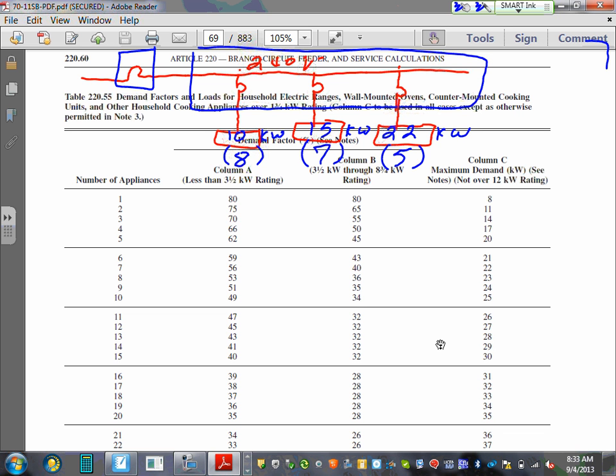Your job is to size the system, right? So our job is to size the system. What I'm going to do first is size the feeder, the 240 feeder that's coming to this panel. You're going to get used to the way I do business, guys. Every time I draw these circuits, everybody knows that this box is actually a circuit breaker box, like the panel. These little bulbs are circuit breakers. The lines represent a branch circuit down here and a feeder down here. Is the terminology clear?